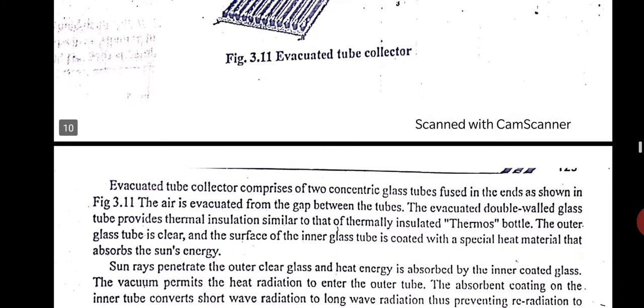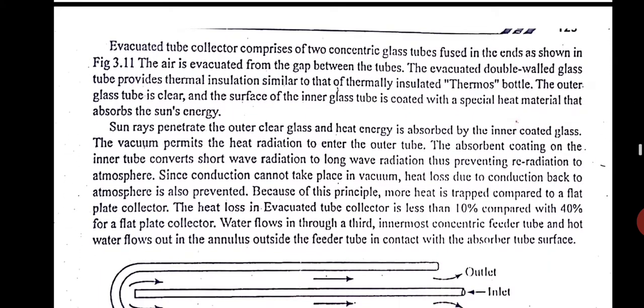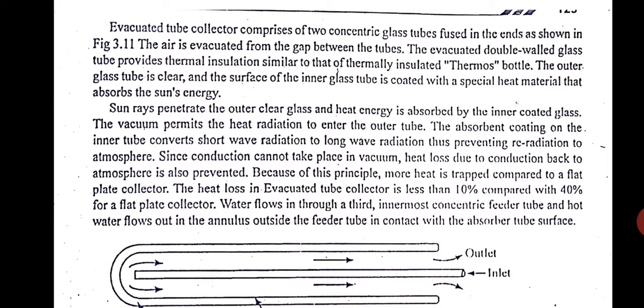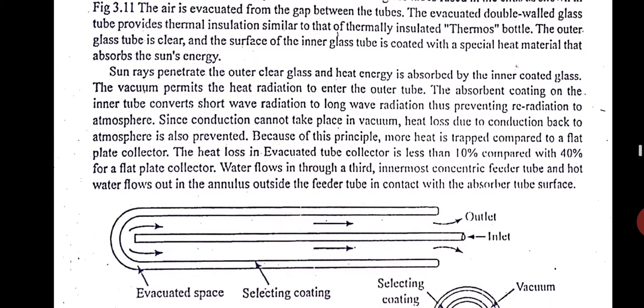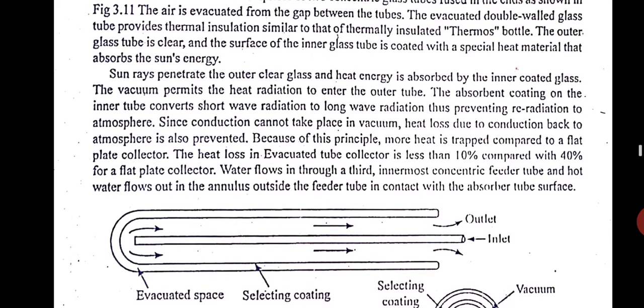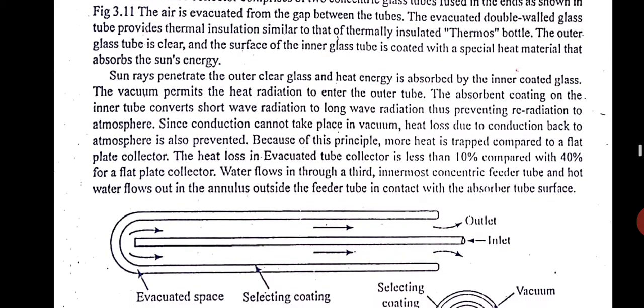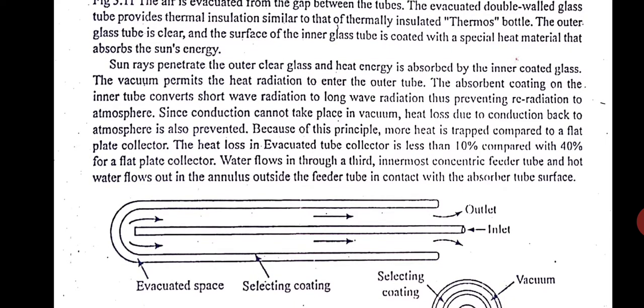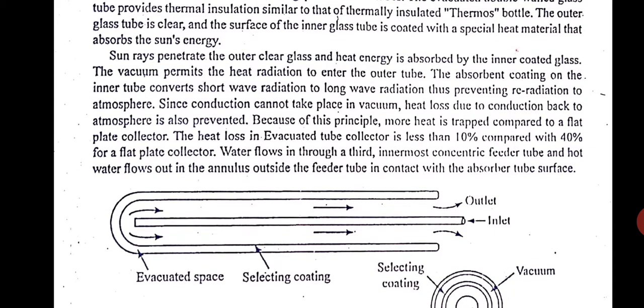The ETC consists of two concentric glass tubes as shown in the picture here. The air is evacuated between the gaps of the tubes. The evacuated double wall glass tubes provide thermal insulation similar to that of a thermos bottle. The outer glass tube is clear, is a plain glass outer glass, and the surface of the inner glass tube is coated with a special heat material that absorbs the sun's energy. You can see here.